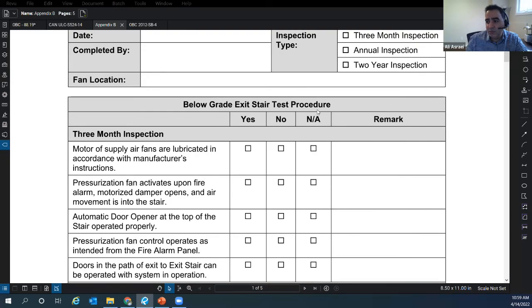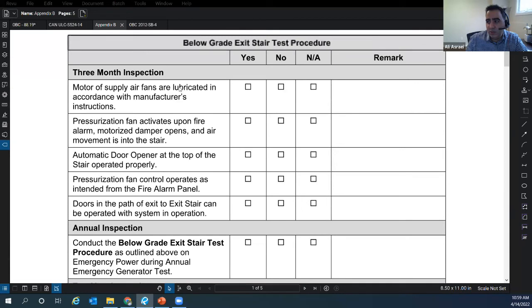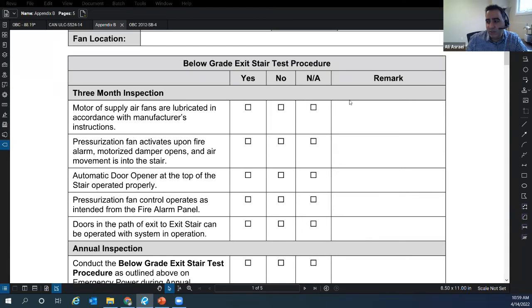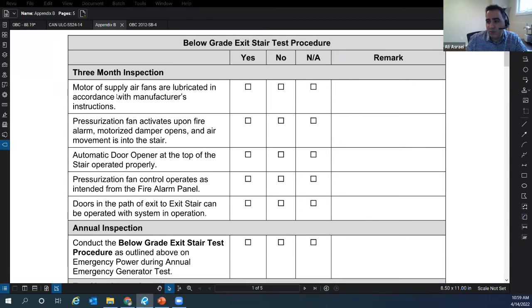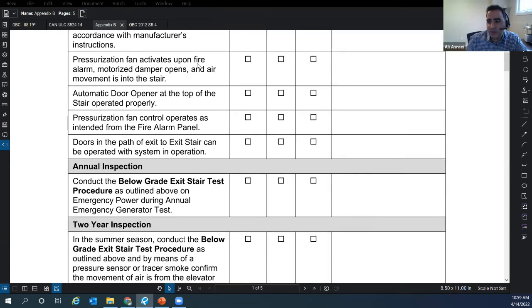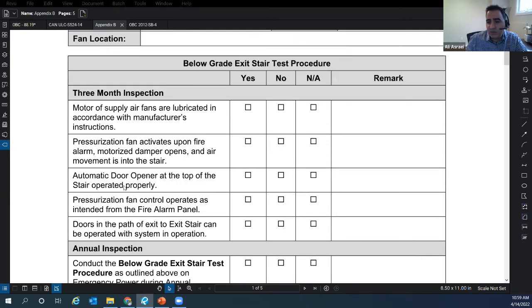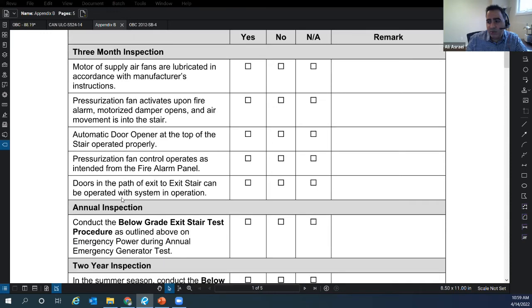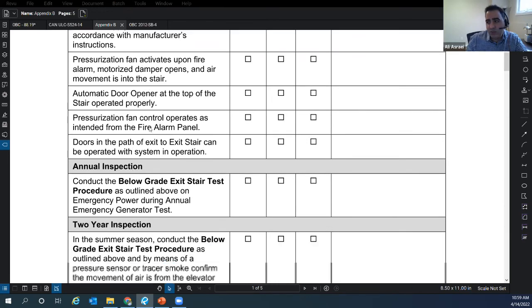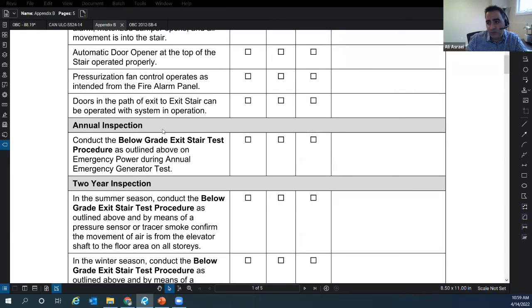This is for the below grade exit stair test procedure. So you have to follow, is it yes, no, or not applicable? Some notes here: motor of supply air fans are lubricated, pressurization fan activates upon fire alarm, motorized damper opens, automatic door opener. This table can change from building to building because there are a lot of different things in different buildings, so you can't have one report, but generally this is what it looks like when you see an annual inspection report from us.